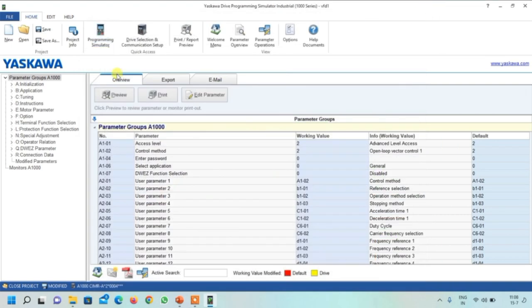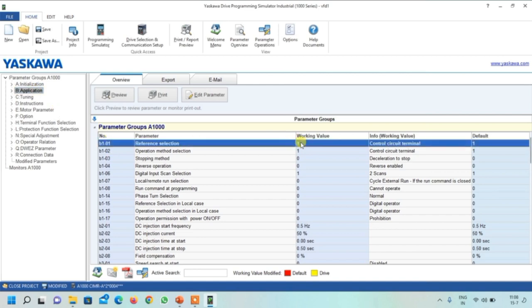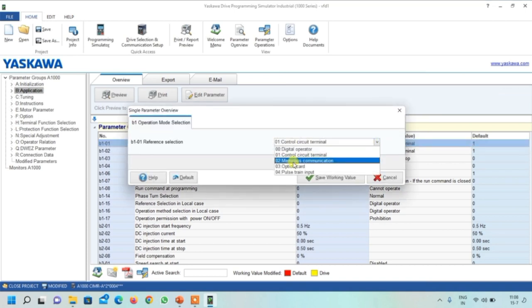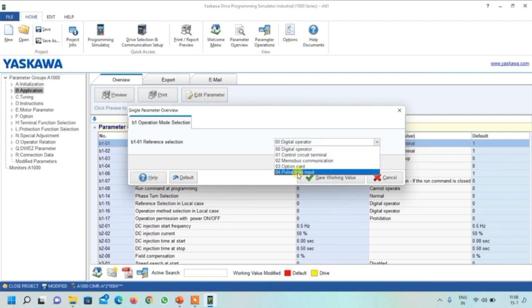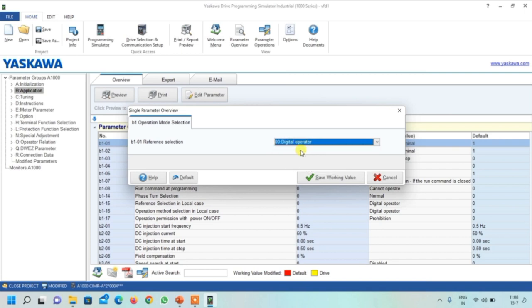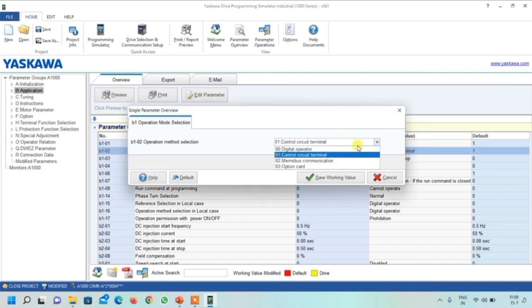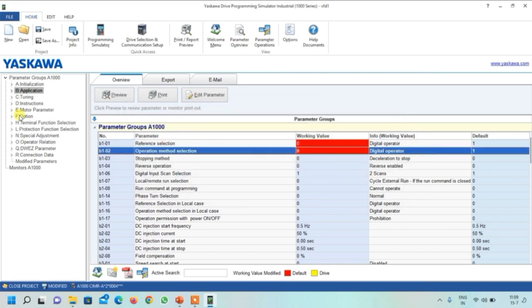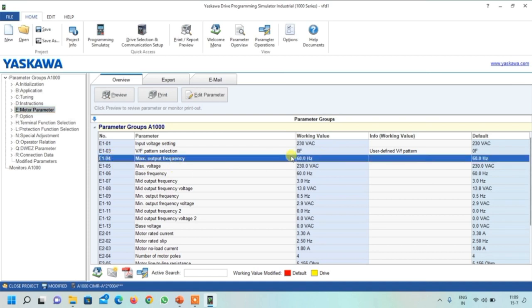Open the Yaskawa software and close the simulator first. Go to parameter b1-01 - to change the parameter, double-click on it and click the list. We are selecting 'Digital Operator.' There are other options but we can't use them, like Modbus. Select it and save. Then go to b1-02 and also select zero, then click Yes.